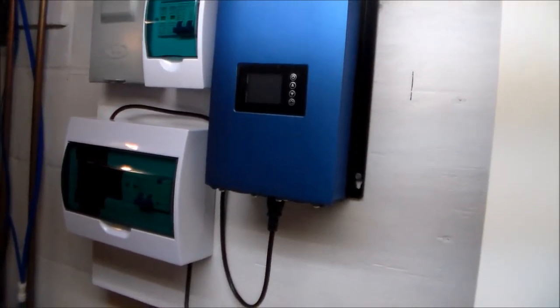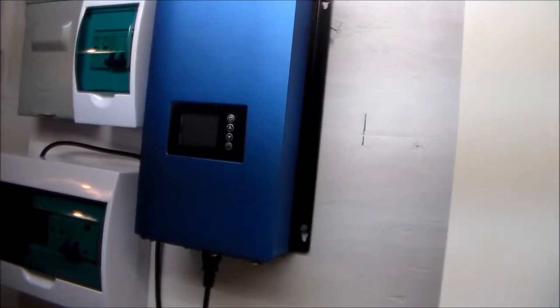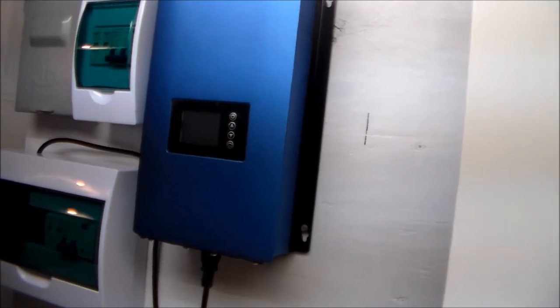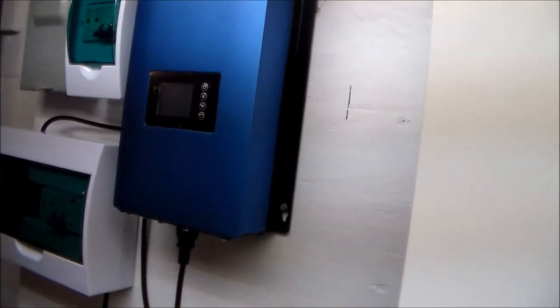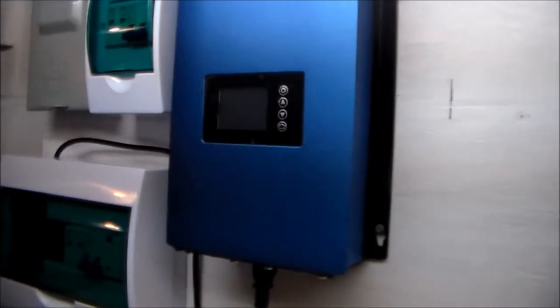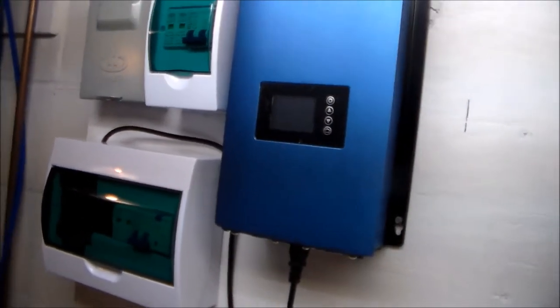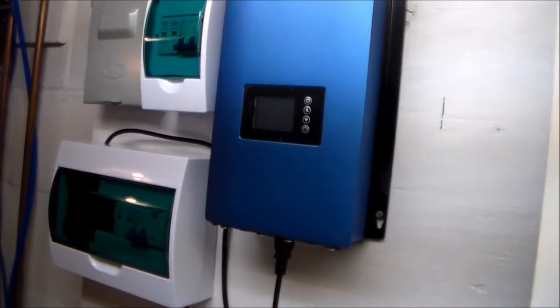For my particular installation, I could have gotten by with 12 AWG wire size. However, I did decide to upgrade it a little bit and use 10 AWG cable, because it's able to handle a little bit more current over a greater distance with less loss, and it wasn't really a whole lot more expensive than the 12 AWG cable was.